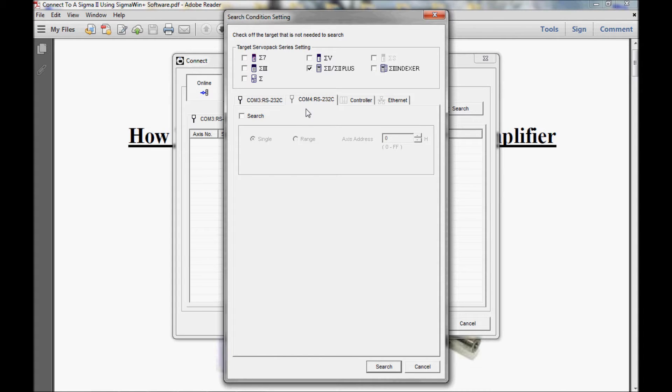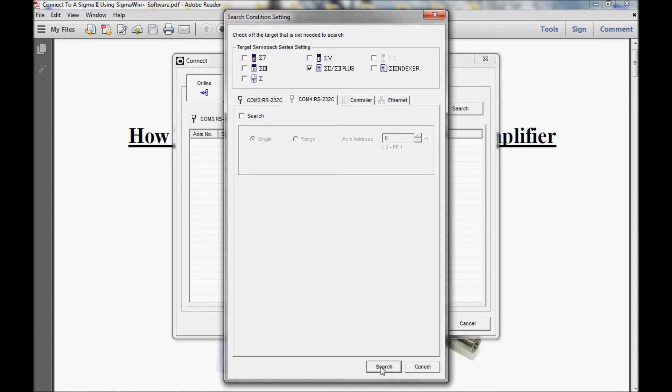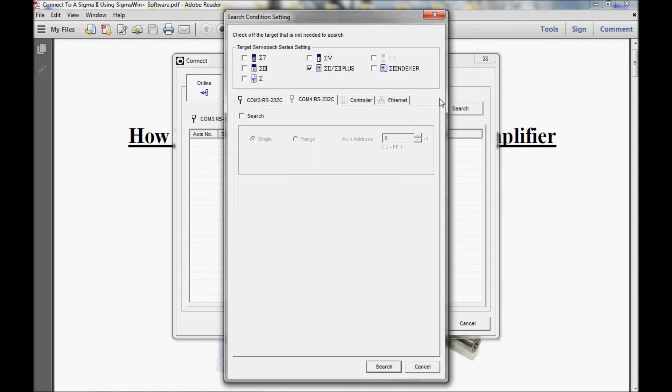In the next section, I have four tabs. The only tab I'm concerned with is the tab I'm going to use to communicate with my amplifier. In this case, I am using COM port 4. In the COM port tab, I have a box with the word search next to it. I want to make sure there is a check mark here. When there is no check mark, this area is grayed out, and if I perform a search, the software will not find the servo pack. So we'll check that theory out real quick.